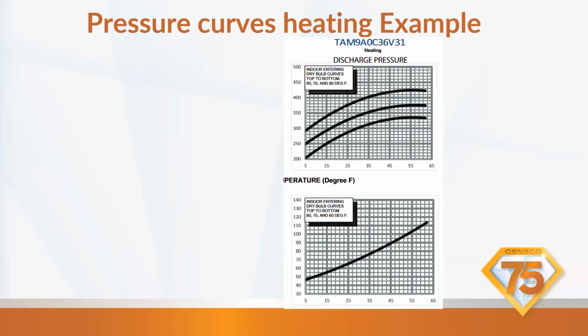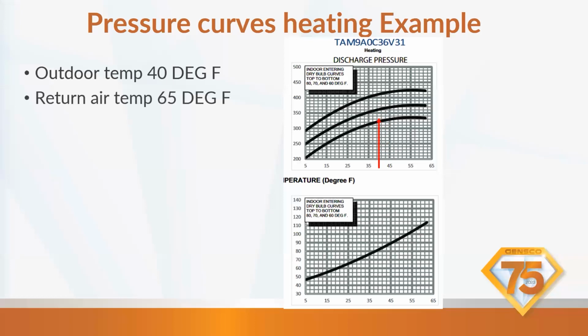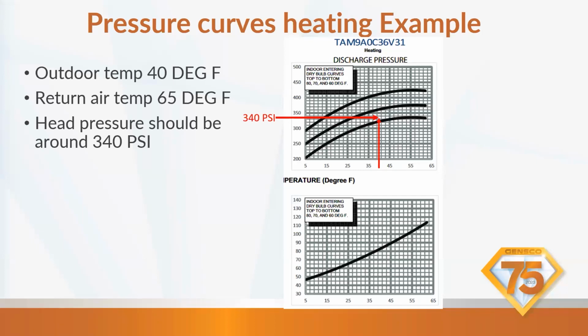So we'll go through a heating example that we will be seeing in the next month. You have an outdoor temperature of 40 degrees. So we look on the graph, we come up on 40 degrees, it is right about here. So we just go up with it. Return air temperature 65. So where does that intersect? We carry it over. We want about 340 PSI on the head pressure. So head pressure should be around 340.